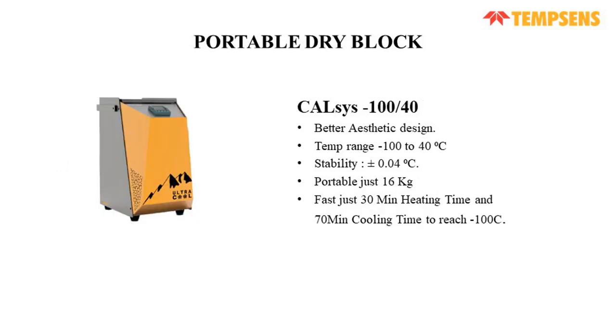Then we have CALsys -100/40. It has a very aesthetic design, and the temperature range for this calibrator is minus 100 to 40 degrees centigrade. The stability is plus minus 0.04 degrees centigrade. It has just 16 kg of weight, and the heating time is 30 minutes. The cooling time is just 70 minutes to reach minus 100 degrees centigrade from the ambient.